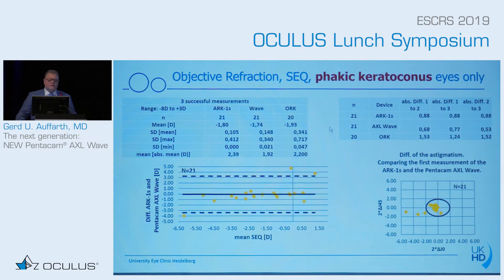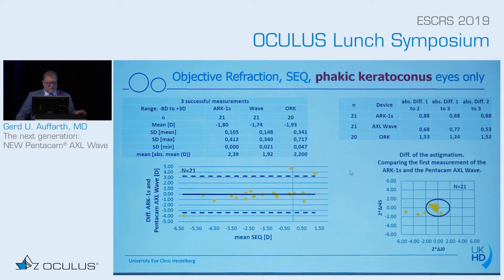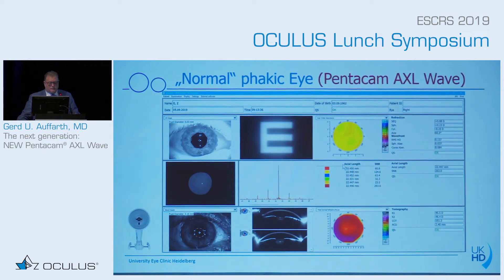However, the Schwind device was in line when we looked at the keratoconus patients. Here we have almost exactly the same values in all three machines, with very good Bland-Altman results. It's quite interesting to see that these different machines measure differently, but we had very good agreement between the Pentacam and the NIDEK device.